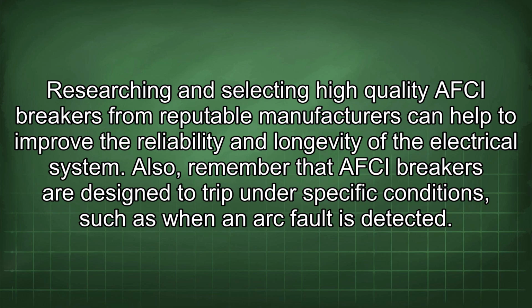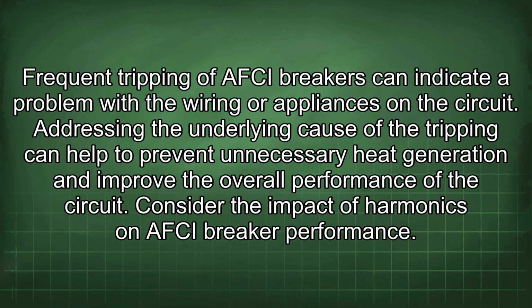system. Also, remember that AFCI breakers are designed to trip under specific conditions, such as when an arc fault is detected. Frequent tripping of AFCI breakers can indicate a problem with the wiring or appliances on the circuit. Addressing the underlying cause of the tripping can help to prevent unnecessary heat generation and improve the overall performance of the circuit.